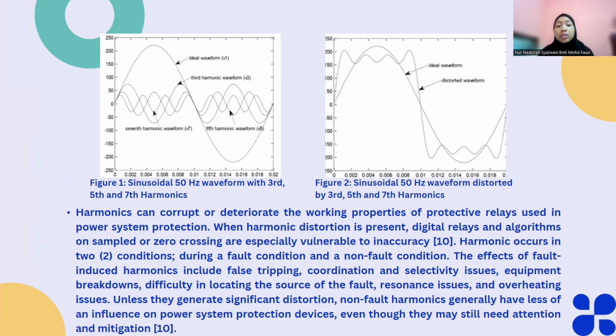Harmonics can corrupt or deteriorate the working of the protection relays used in power system protection. When harmonic distortion is present, digital relays and algorithms based on sampling are especially vulnerable to inaccuracy.